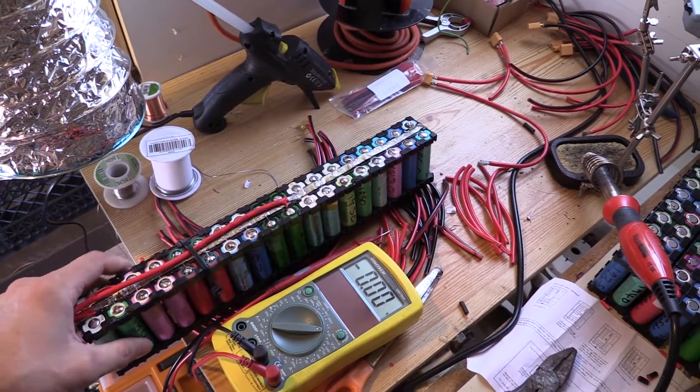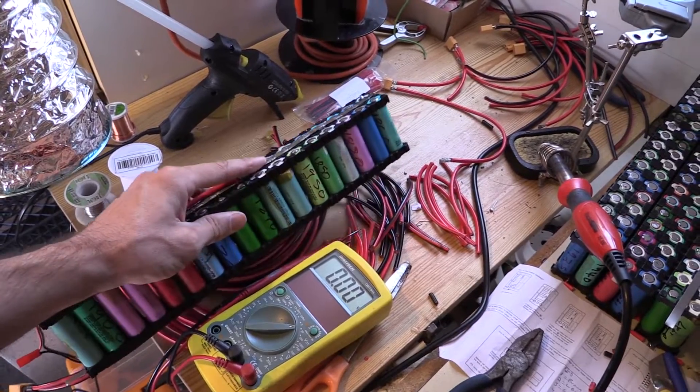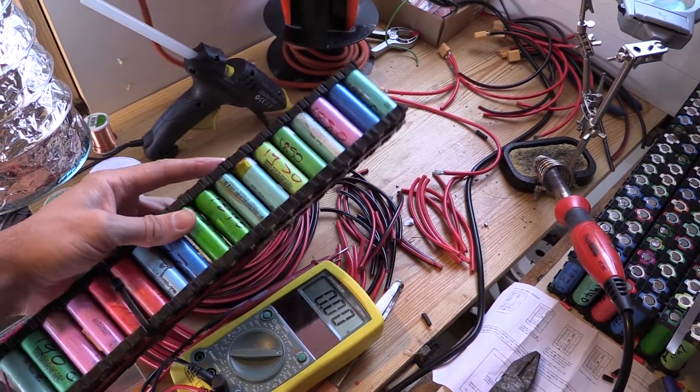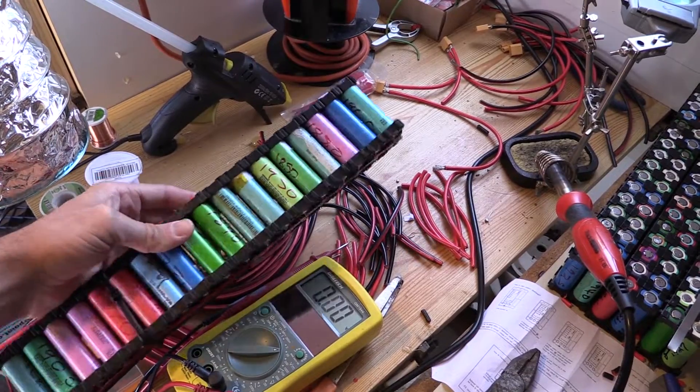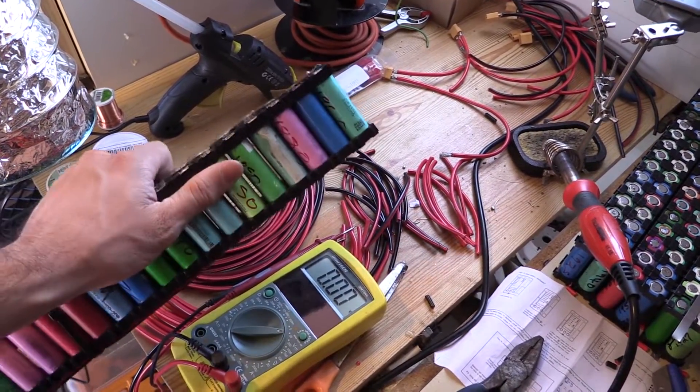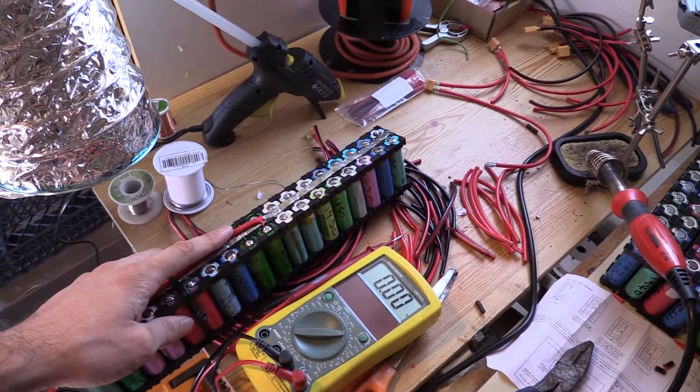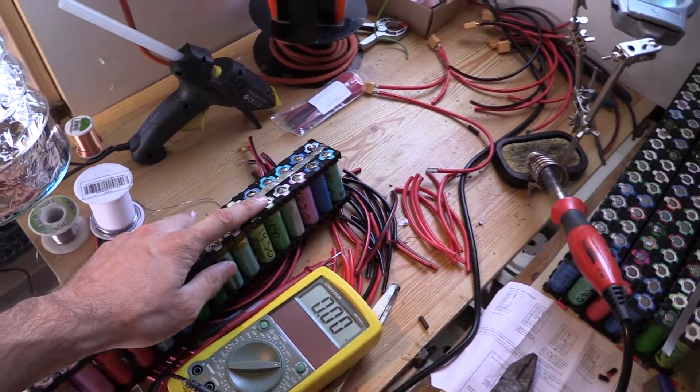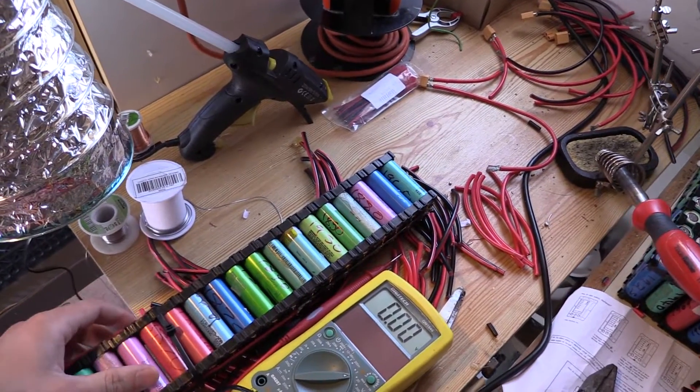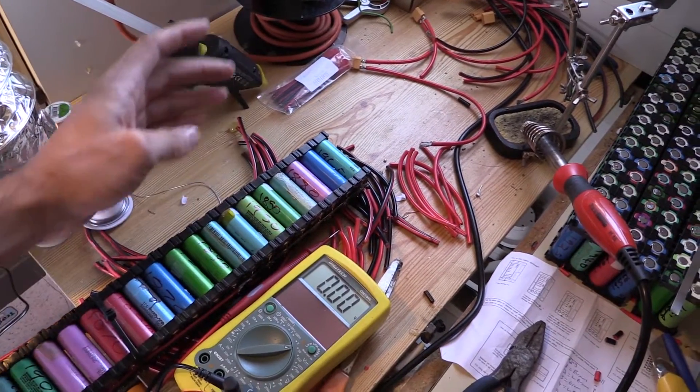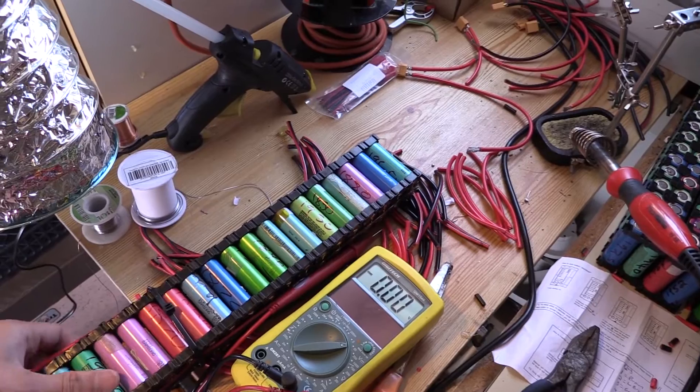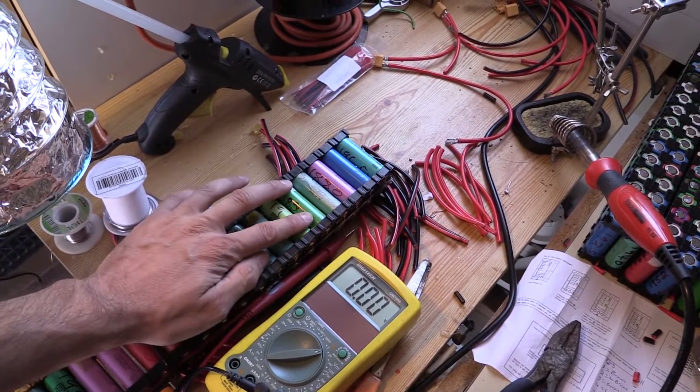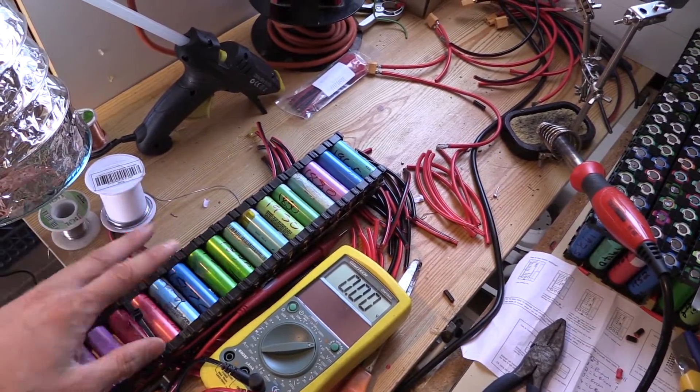That brings us to a couple of things. First, the fuses only protect the pack from a cell going short circuit. That's all they do. It's very important to put a fuse on in case a cell goes short circuit, because there's a lot of current in the pack and you don't want that going through one particular cell.